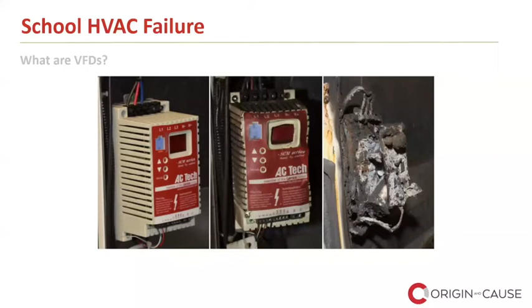So as I mentioned in the background information, there was a power outage immediately before the failure was discovered. This incident occurred in British Columbia. So information from BC Hydro, which is a Crown corporation, is available through a FOIP request, a Freedom of Information request. That data does include smart meter data. As I was representing the school district, it was easy to get their permission as account holders for BC Hydro to release that data. So the power records that we obtained indicated that one of the 3 phases completely failed during the outage, while the other 2 remained on. Power on the phases that remained on dipped by up to 75% of nominal voltage.